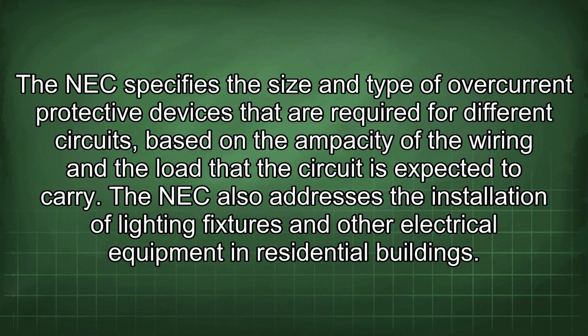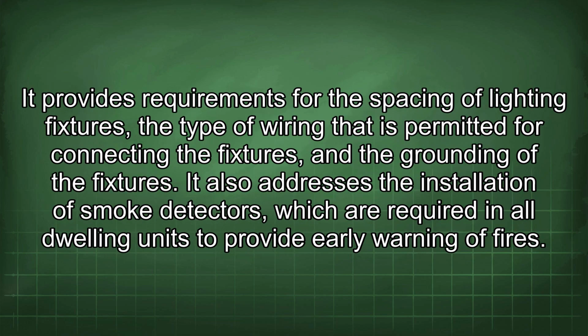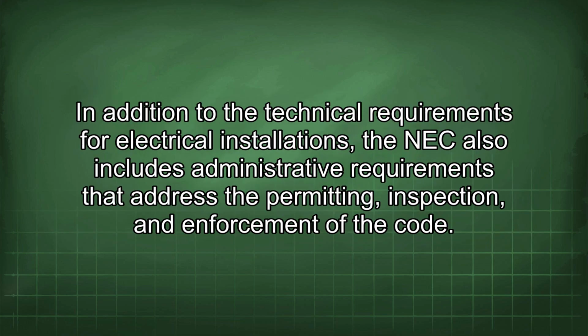The NEC also addresses the installation of lighting fixtures and other electrical equipment in residential buildings. It provides requirements for the spacing of lighting fixtures, the type of wiring that is permitted for connecting the fixtures, and the grounding of the fixtures. It also addresses the installation of smoke detectors, which are required in all dwelling units to provide early warning of fires. In addition to the technical requirements for electrical installations, the NEC also includes administrative requirements that address the permitting, inspection, and enforcement of the code.